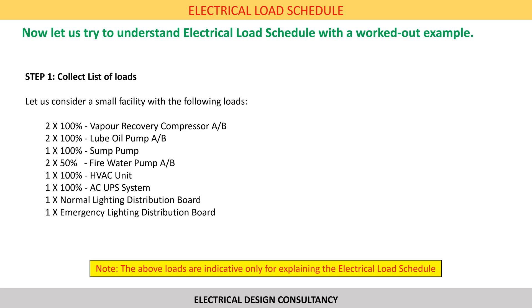To start with, we need to collect the electrical loads of the plant. For our example let us consider a small facility with the following loads: 2×100% vapor recovery compressors, 2×100% lube oil pumps, 1×100% sump pump, 2×50% fire water pumps, 1×100% HVAC unit, 1×100% AC UPS system, 1 normal lighting DB, 1 emergency lighting DB. The loads indicated here are indicative only for explaining the load schedule calculation.